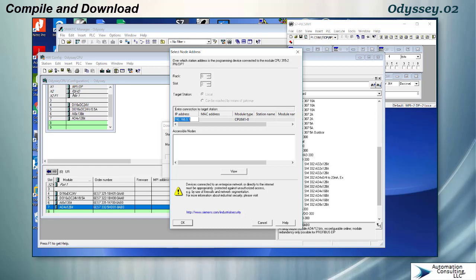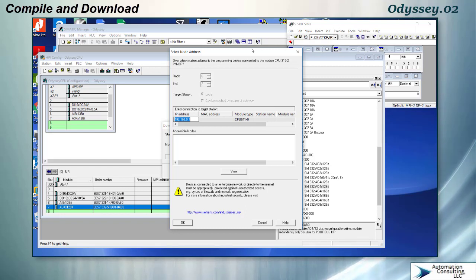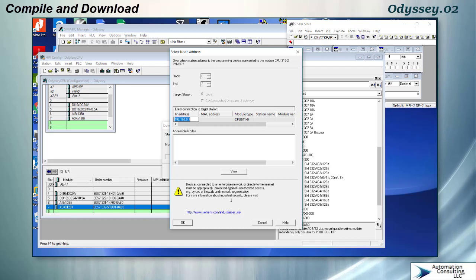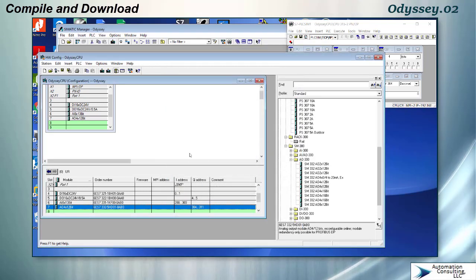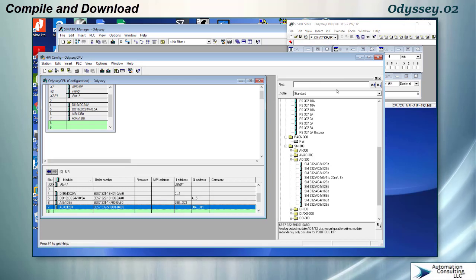It shows the address that I configured in my processor here and you notice that it also shows CPU 841, it always shows that for a simulator. This is not a real PLC, this is a little fake PLC but it's a pretty awesome one, it works very well. It remembers the address that I configured in the hardware and downloads it to the simulator. You have to have the simulator open when you do this. I'm going to say okay and you notice it did a little bar graph and it's in there. At this point I have saved, compiled, downloaded so I can close my hardware.